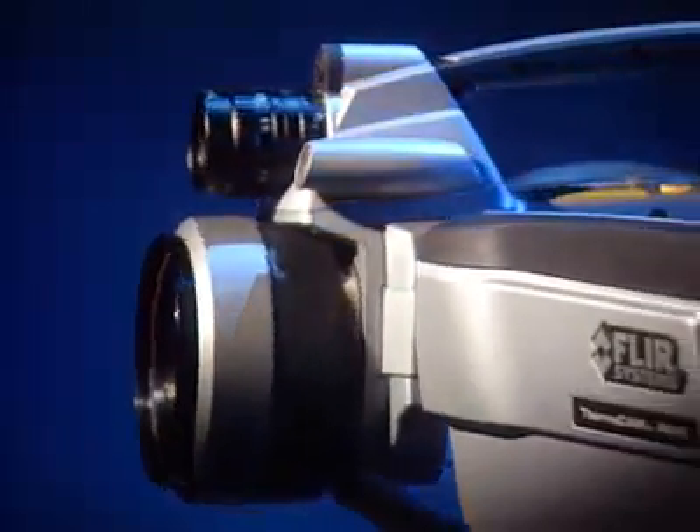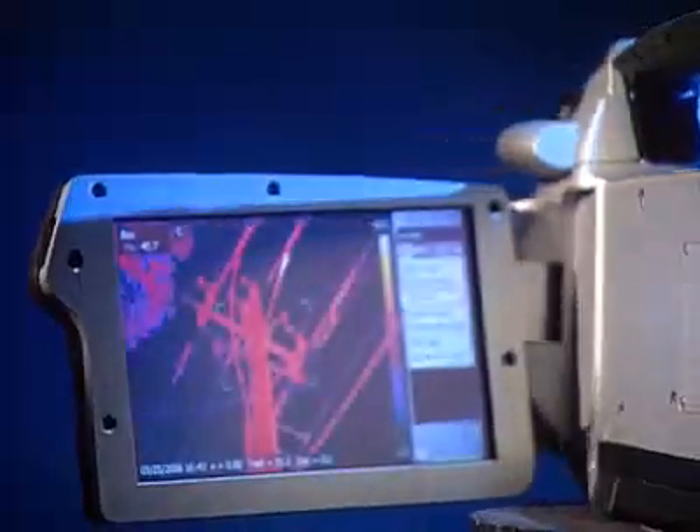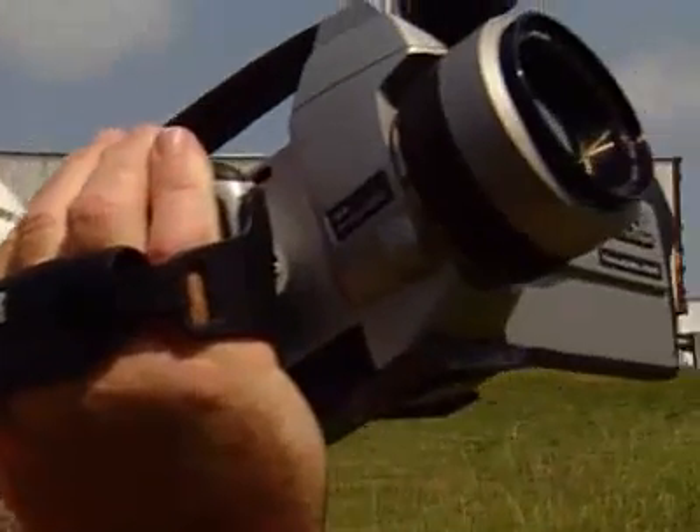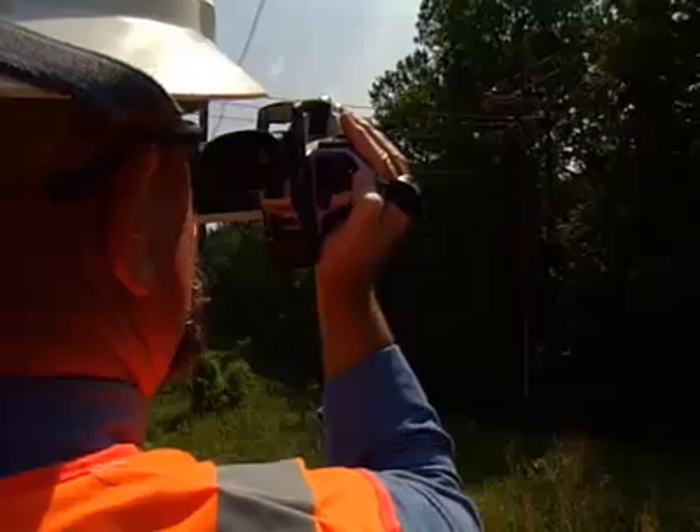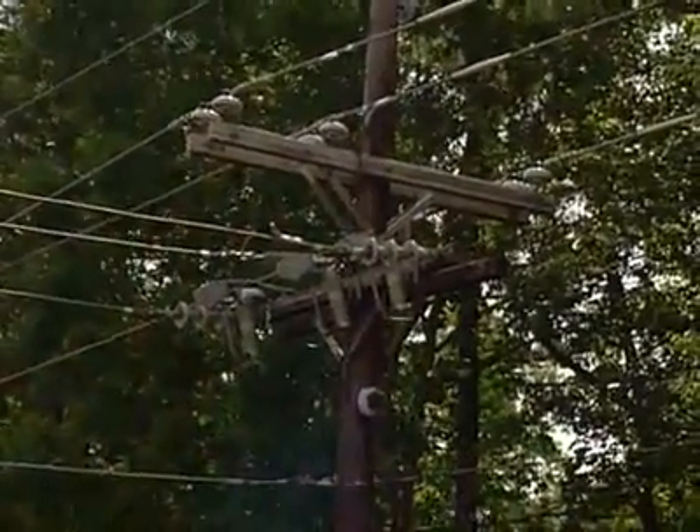When we are teaching about the P640, it has a 640x480 resolution, which means it has 307,000 plus pixels. For the user, that means with the same field of view, you have a lot more resolution. The FLIR P640 has a sharp, crisp image. I'm getting better accuracy in my delta temperature. It helps me analyze my equipment better. I can tell exactly where the problem is, and it cuts down on time in the field.